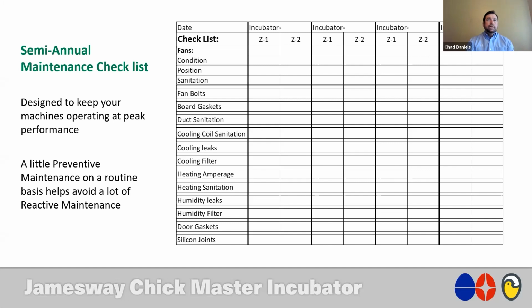And so when we look at the details around this specific check sheet, of course it's an Excel spreadsheet. And if you'd like to have a copy of that, you can definitely request that, and we'll make sure we send that to you independently. But this check sheet, as you can see in the beginning, and this is just the top portion of it, I have it set up where you have the ability to have 4 incubators on this sheet. You may want to add a 5th incubator on there, but that way you can do multiple incubators on one individual sheet. You don't have to have a sheet on a per machine basis, but you can most certainly modify the sheet to fit your application and do it however you would like.